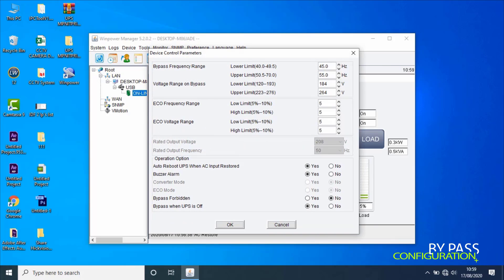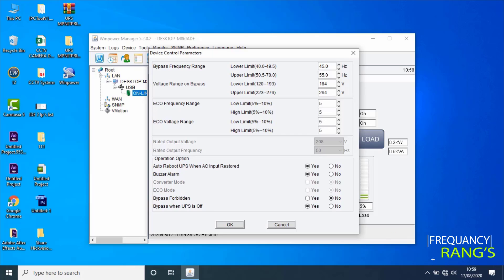Here the user can configure bypass, eco mode, and operation settings such as buzzer, auto reboot, voltage, and frequency ranges, as per site requirements. Once settings are done, click OK.